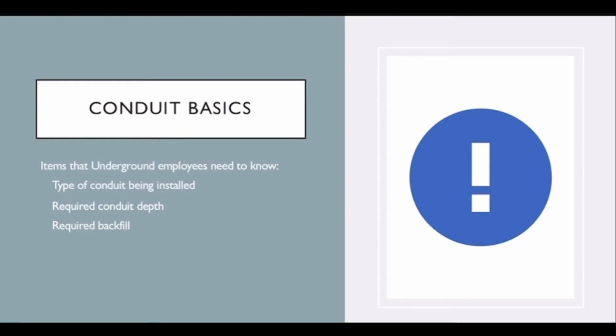Required backfill is also important. Typical installation can be backfilled with the spoils removed from the trench unless that backfill is not suitable for replacement. An example of this would be if there was a lot of rock removed. The rock in backfill can damage the conduit if put back in the trench and compacted. If that is the case, suitable backfill such as sand will be brought in. In many cases, there are specific backfill requirements for conduit that are project specific, such as sand, flow fill, or concrete encased.